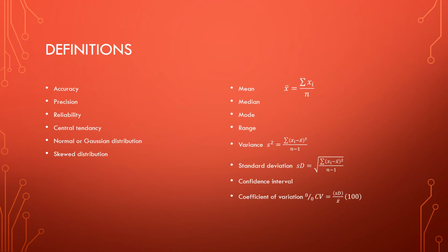2 different means. Well, how can I determine how much variation there is between these 2? Coefficient of variation allows you to compare these two. And if you get a number that is less than 5% for the coefficient of variation, that's what we're looking for: acceptable variation between two different procedures.